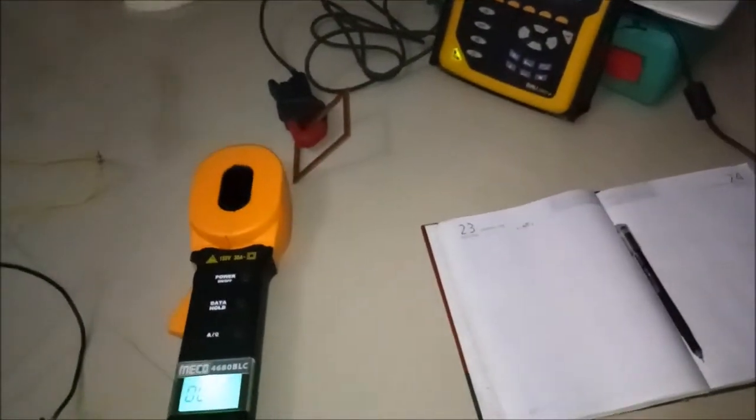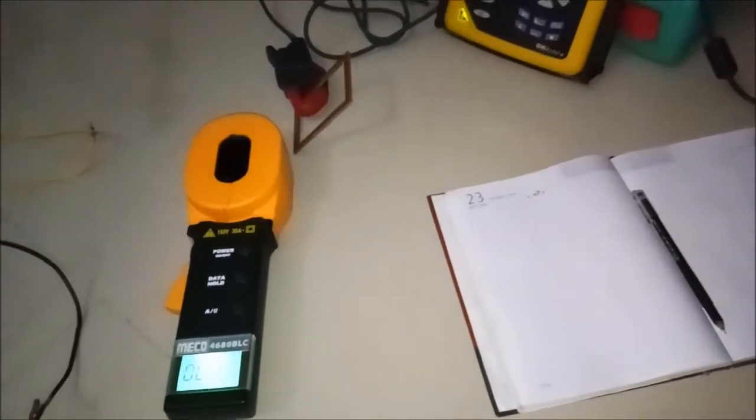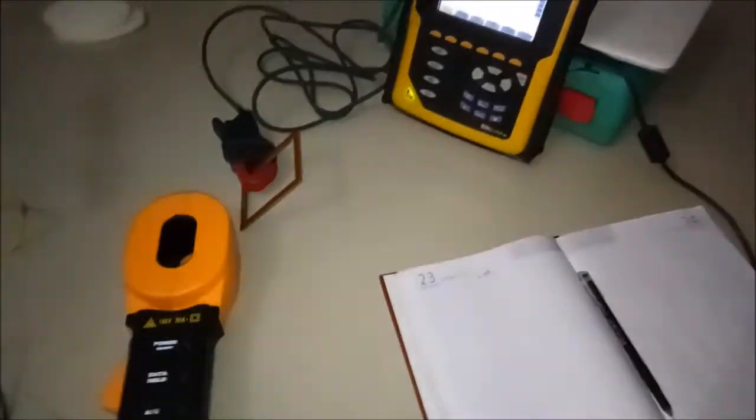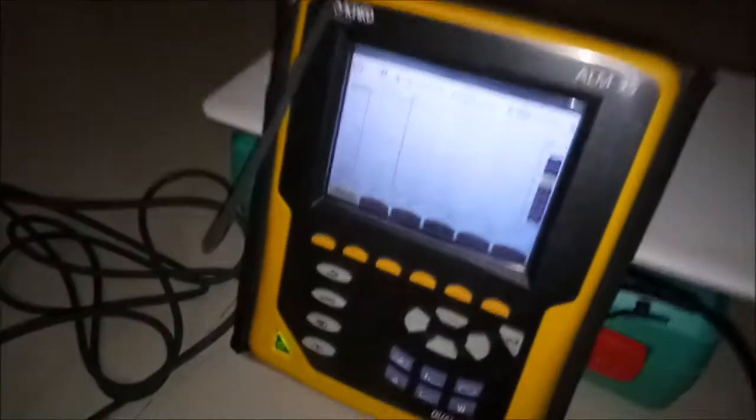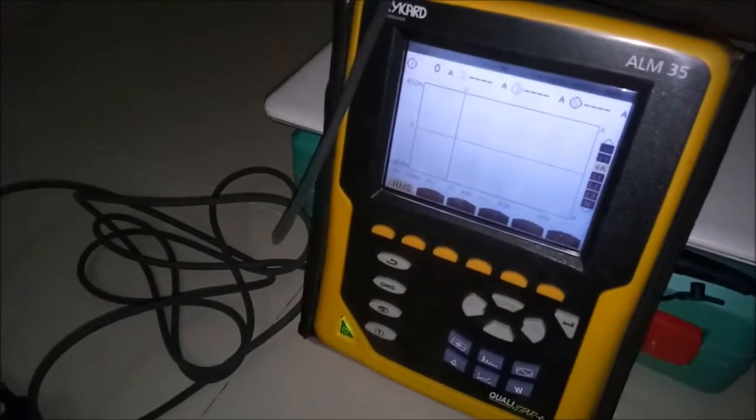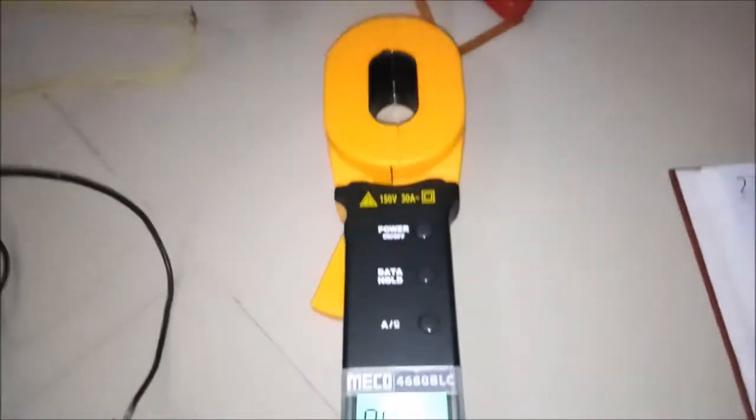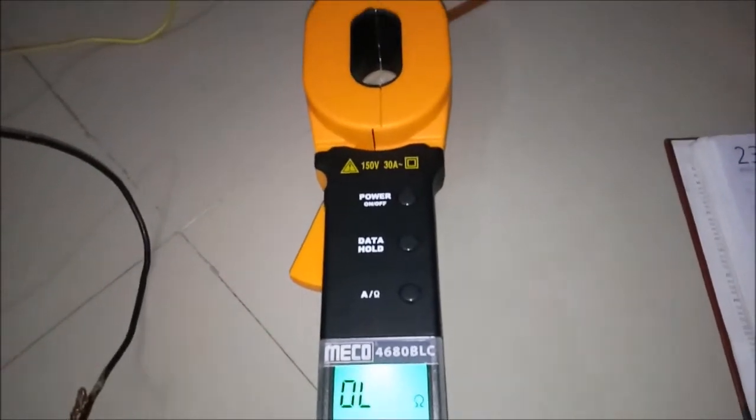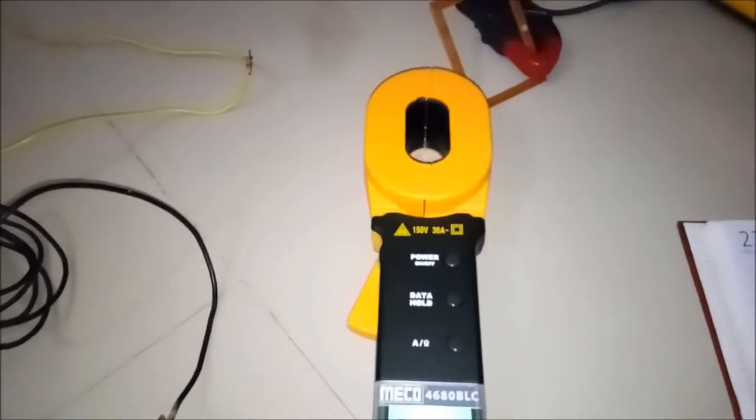Hello, this video intends to explain you how does the clamp-on earth tester work. So here we have made a small setup wherein we have got this 5 ohm resistor loop, then we got an analyzer to measure the current, and we got this Meco make clamp-on earth tester.